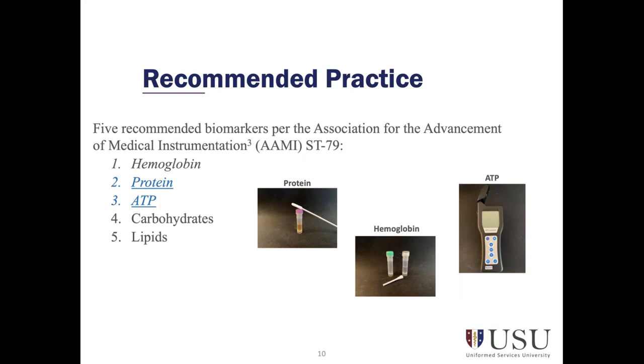According to AAMI, multiple studies have indicated that hemoglobin, protein, ATP, carbohydrates, and lipids are useful markers for bioburden detection. The ATP technology involves the swabbing of the instrument, the addition of a reagent, luciferase, luciferin, and a placement into a handheld device that measures the amount of light, relative light units, RLUs, that is emitted. The number of RLUs correlates to the ATP level and bioburden load. For surgical instruments, the recommended passing RLU benchmark, and this is the benchmark for the Ruhof ATP Complete, is 99 RLUs or less. If the RLU score is above 99, the surface harbors organic matter and is considered contaminated and should be re-cleaned. Now, just for clarity, this is the tool that I use for this particular project.